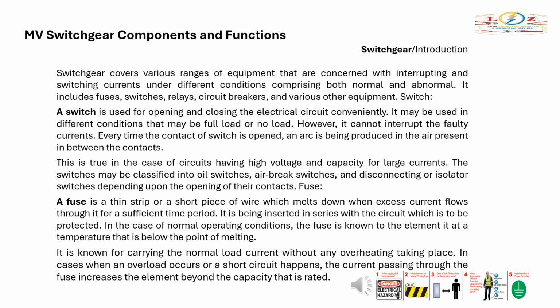Switch. A switch is used for opening and closing the electrical circuit conveniently. It may be used in different conditions that may be full load or no load. However, it cannot interrupt the faulty currents. Every time the contact of switch is opened, an arc is produced in the air present in between the contacts. This is true in the case of circuits having high voltage and capacity for large currents. The switches may be classified into oil switches, air break switches, and disconnecting or isolator switches depending upon the opening of their contacts. Fuse.